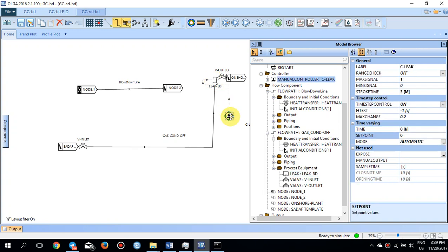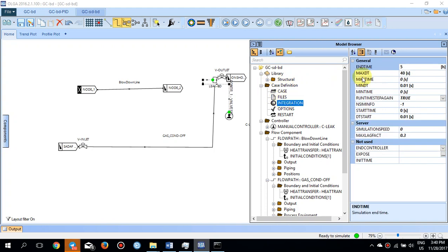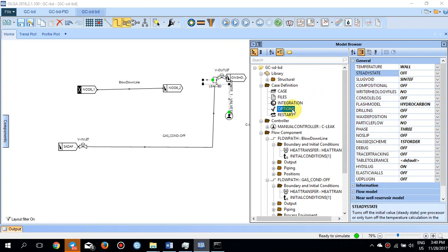The set point of this manual controller is set to zero, which means the leak is out of the simulation and not working. I'm running this case for five hours — four hours with the line shut down. I need to set the steady state solver to off because the blowdown line has no mass source, so the steady state solver has difficulties starting this case.